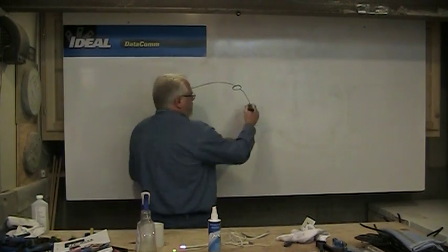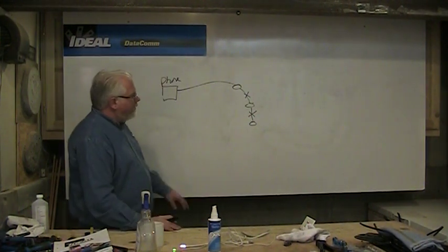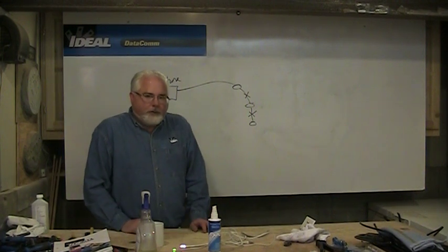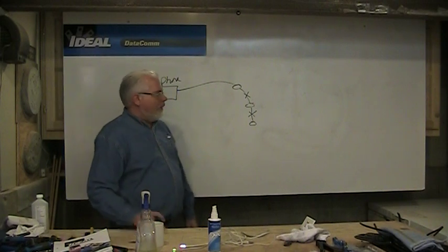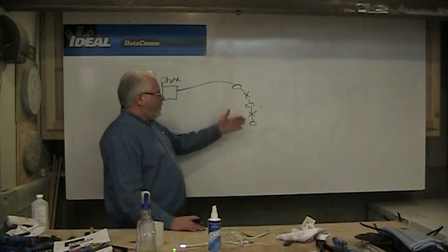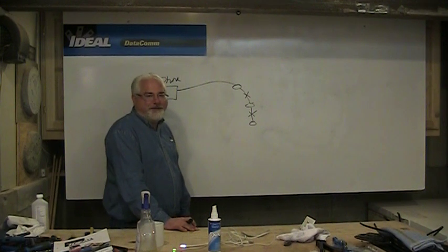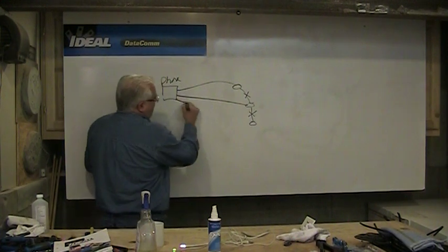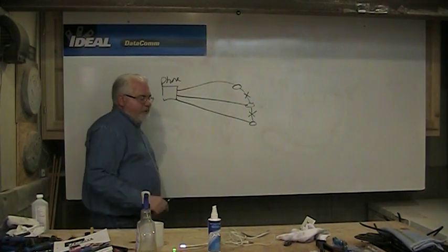And the standards do not recommend this at all today for several reasons. One is anytime you splice wire, you're messing with its ability to do what it's got to do. Computers can't be wired this way. There's another reason that's a problem. And then if you're troubleshooting things like this, this is a pain to troubleshoot because you have no idea where the splices are. Where if I've home run my cable, which is what we want you to do, I know where both ends of this cable is. So it gets a lot easier to troubleshoot.